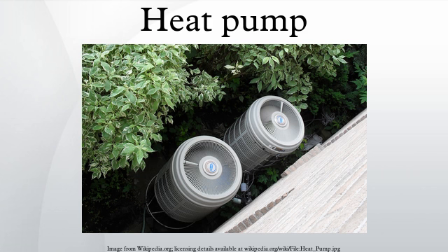Reversible heat pumps work in either thermal direction to provide heating or cooling to the internal space. They employ a reversing valve to reverse the flow of refrigerant from the compressor through the condenser and evaporation coils. In heating mode, the outdoor coil is an evaporator, while the indoor is a condenser. The refrigerant flowing from the evaporator carries the thermal energy from outside air indoors, after the fluid's temperature has been augmented by compressing it. The indoor coil then transfers thermal energy to the indoor air, which is then moved around the inside of the building by an air handler.